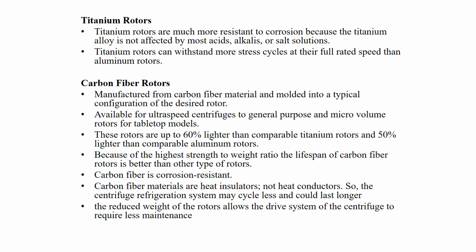The latest addition is carbon fiber rotors. This has got several other advantages. First of all, it is lightweight. So since it is lightweight, it has got less impact on the motor and the shaft of the centrifuge. It can withstand high stress. So therefore the lifespan of the centrifuge can be increased. It is corrosion resistant.